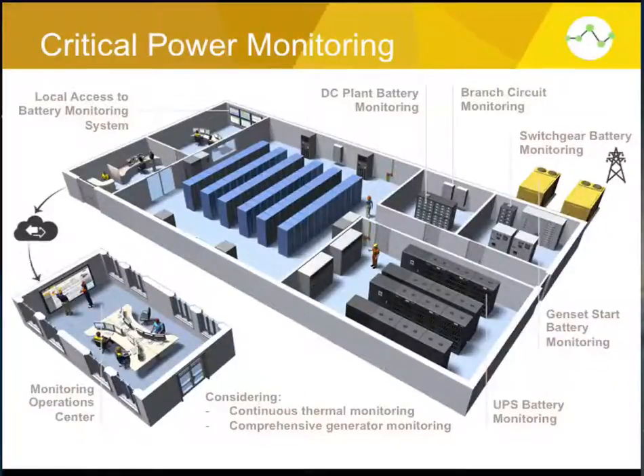One is thermal monitoring, and this is done typically today via manual effort. Somebody will walk around with an infrared scanning gun and look for areas in the data center, for critical power joints, where there might be heat buildup. Heat buildup is indicative that there is a faulty joint, that there's too much resistance.